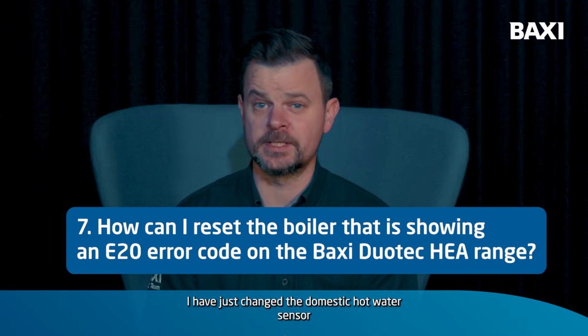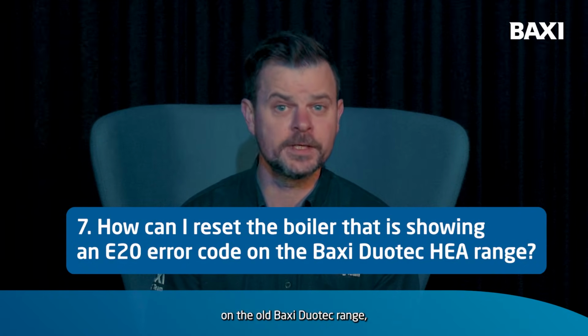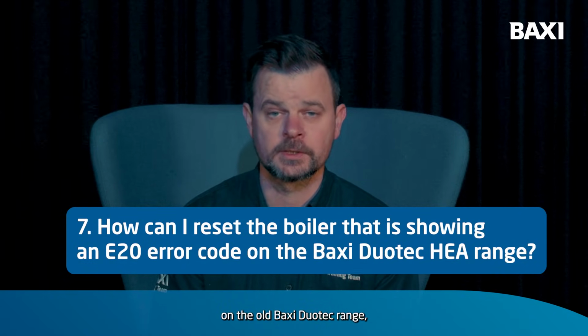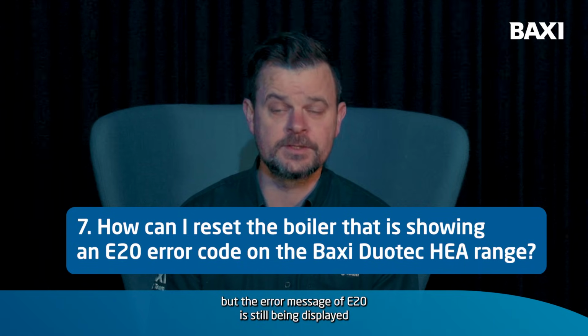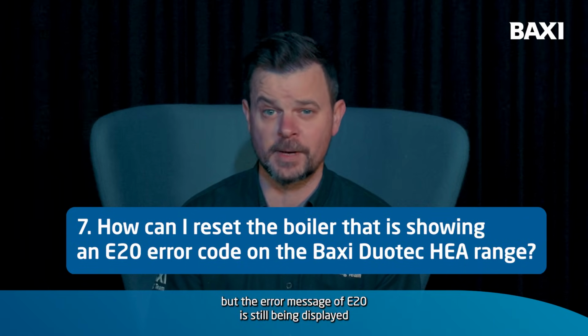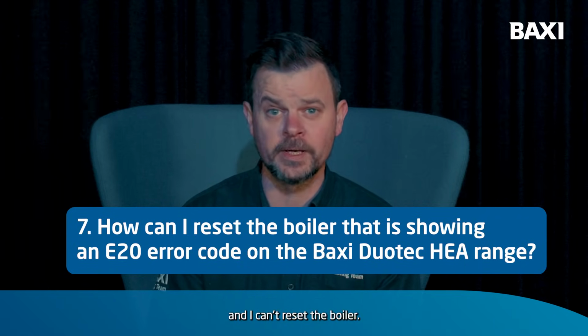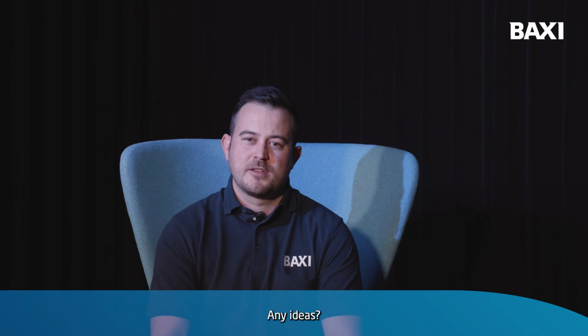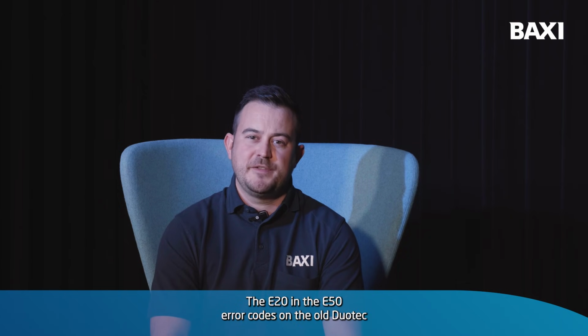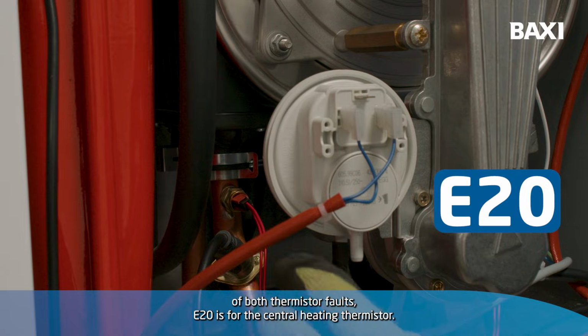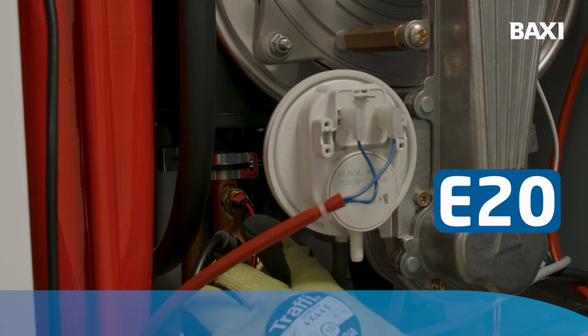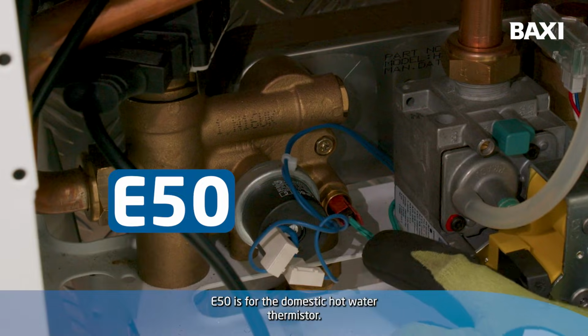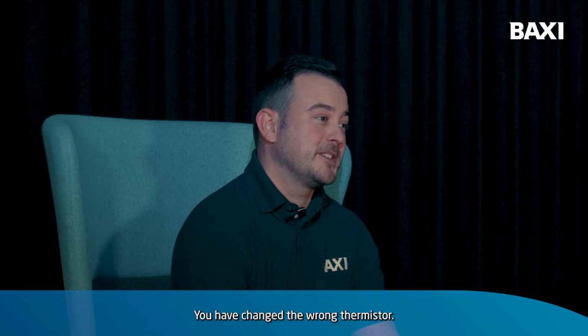Question number 7. I have just changed the domestic hot water sensor on the old Baxi Duotec range, but the error message of E20 is still being displayed and I can't reset the boiler. Any ideas? The E20 and the E50 error codes on the old Duotec are both thermistor faults. E20 is for the central heating thermistor, E50 is for the domestic hot water thermistor. You have changed the wrong thermistor.